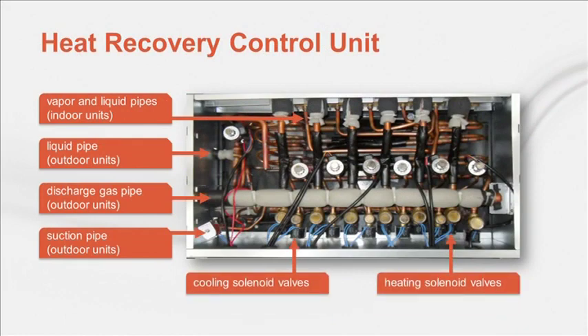These devices have 3 refrigerant pipes connecting it to the outdoor unit, one for discharge gas, one for suction gas, and one for liquid, and there are 2 refrigerant pipes connecting the indoor units to this module, one vapor and one liquid. The system control determines if the indoor vapor port is connected to the discharge or the suction gas, based on whether it's in cooling or heating mode. But the heat recovery control unit can even do more. It can take the waste liquid from a heating zone and direct it to a cooling zone. This is how simultaneous heating and cooling is accomplished.